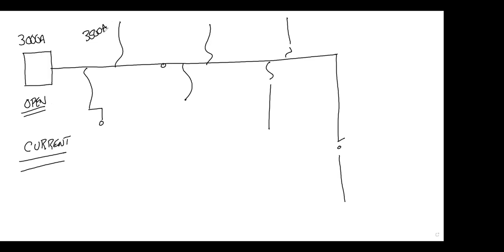Now, if there is 3,500 amps of load existing on my circuit, it can consume that much. Is my breaker in overload even when it's open? Yes. Not really. Sure is. Oh, you said 3,500. Oh yes, it's an overload. It's still breaker overload. Is current flowing? No, my breaker's open. Current is not flowing. So that's breaker overload.